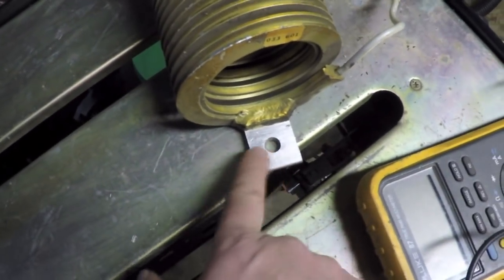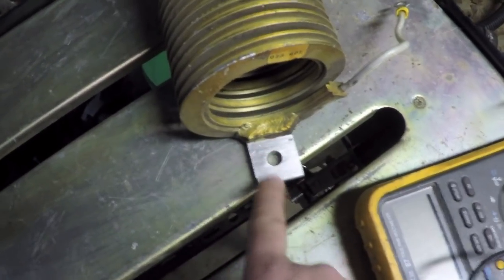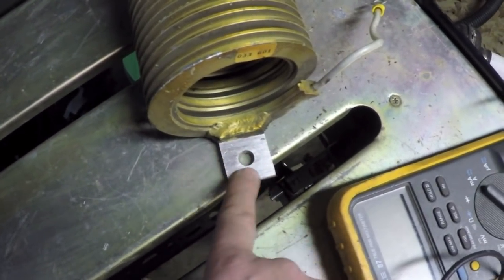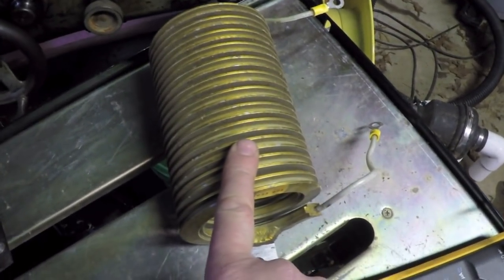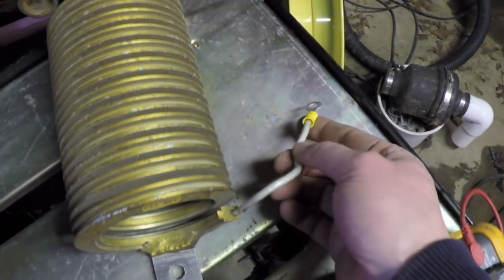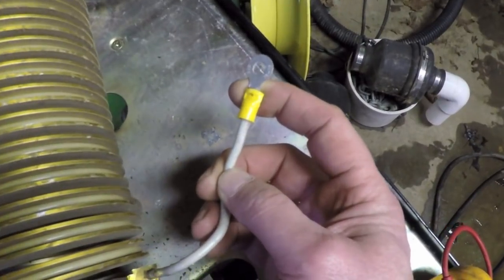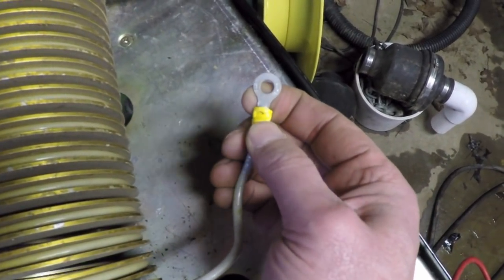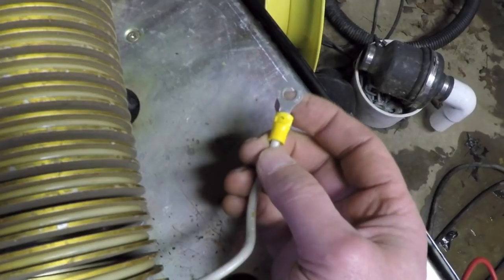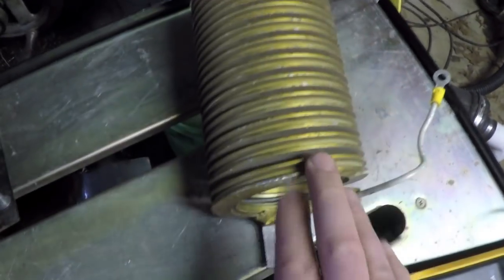So I cleaned up the connection areas on the coil - they're nice and shiny metal now, and I'm ready to install this coil into my Airco. I also had to put new ring terminals on, because the hole size on the terminals that were on here was too small for the studs in this unit. Other than that, the coils were identical.